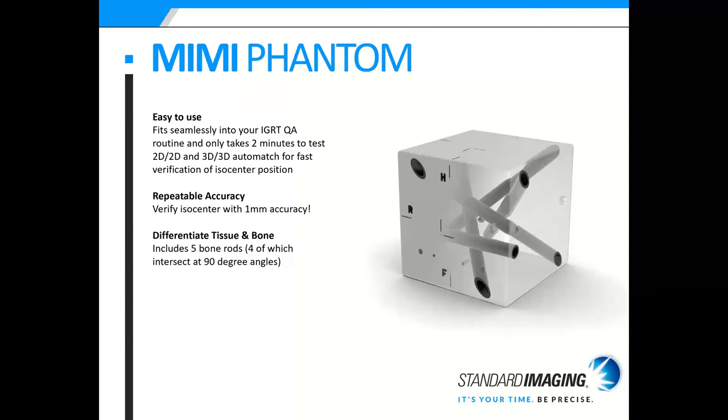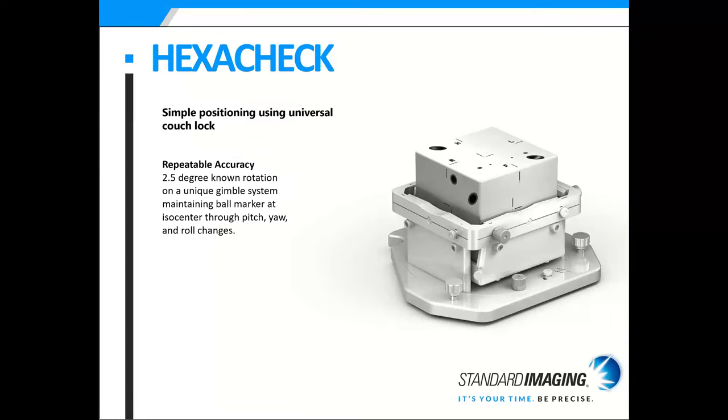The MIMI Phantom is our IGRT QA phantom, which therapists can easily integrate into their daily QA. It does 2D and 3D QA, enabling fast verification of the isocenter position and is accurate to one millimeter. You can differentiate between tissue and bone with the five bone rods, four of which intersect at 90-degree angles. If you have a 6D couch, you can insert the MIMI into the HexaCheck device, which works on a gimbal system with a known 2.5-degree rotation, and it's great for saving time — you can verify pitch, roll, and longitudinal/lateral directions, all six directions at the same time. It's super easy to place on the couch using your universal couch lock.